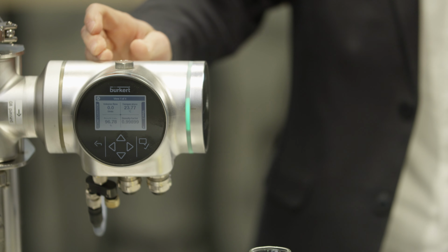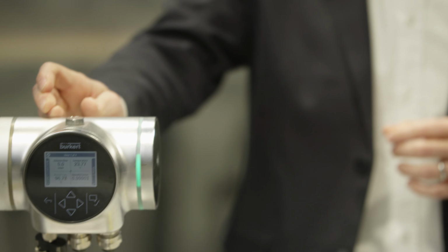And third, FlowWave has even more exciting features and diagnostic functionalities. In one device, you get the measurement of flow, temperature, density factor, and acoustic transmission factor. Density factor and acoustic transmission factor can be used to detect the change from one liquid to another inside the pipe. Now we're going to take a look at how it works.